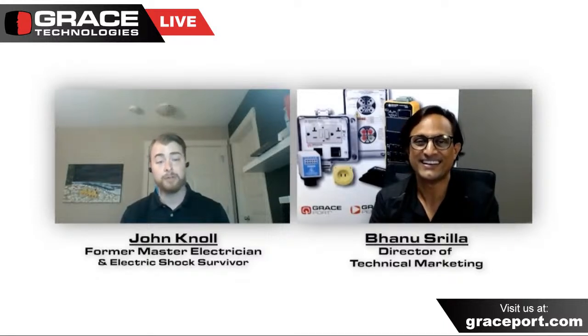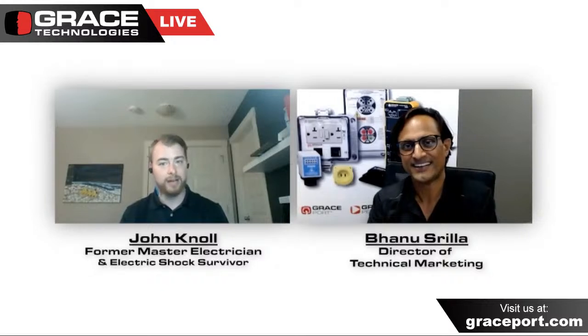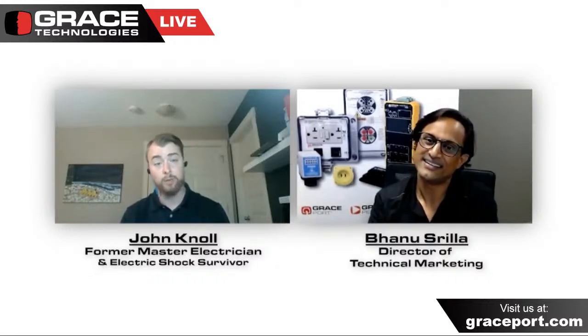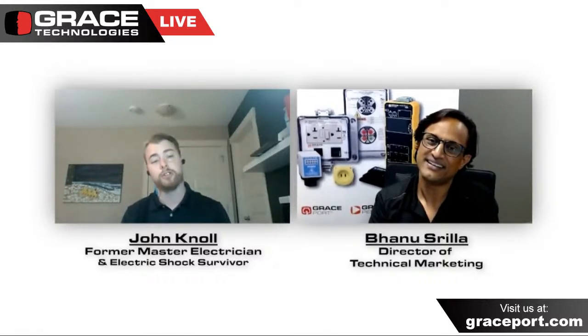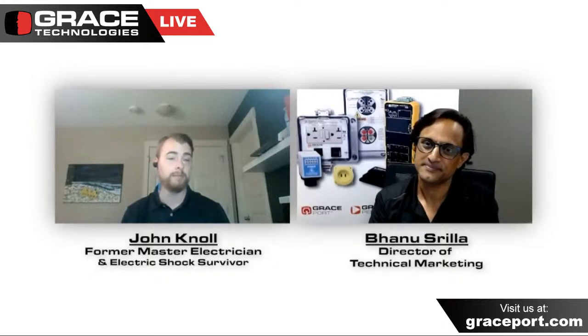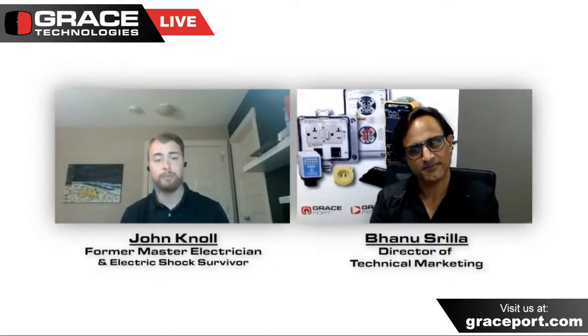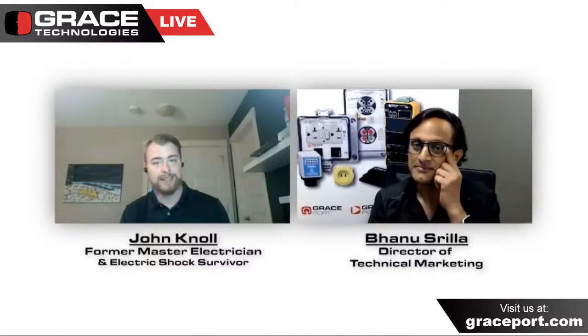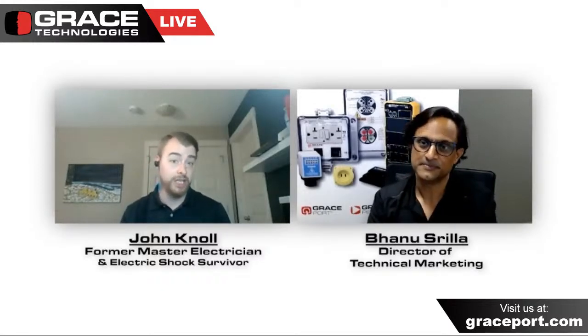From a vendor's perspective as well, in the last decade we adopted the arc fault regulation. That was a big stepping stone because it took the price of a breaker from about $7 up to closer to $40 or $50. But now that we've already absorbed that huge cost, manufacturers should consider that since AFCIs are already in place, it's only about $7 more to add GFCI as well.